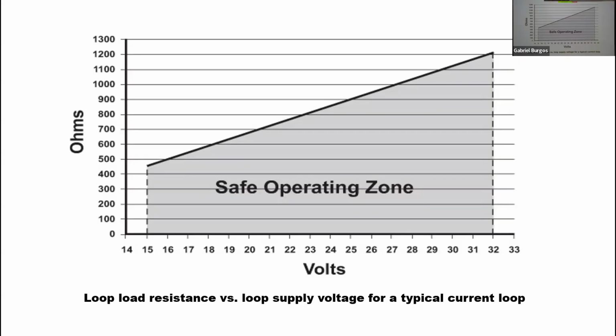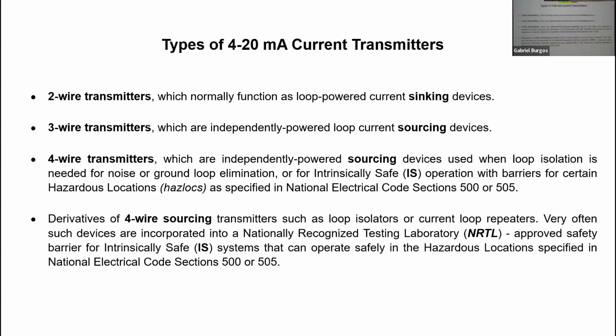So, all right, now let's go to the nitty gritty. There's three general kinds of current transmitters. This device is called a transmitter by the people that use them. That happens to have stuck over the years with the industry, especially in the process industry. So they refer to a pressure transmitter or a flow transmitter or a temperature transmitter. They're all producing 4 to 20 milliamps, okay?